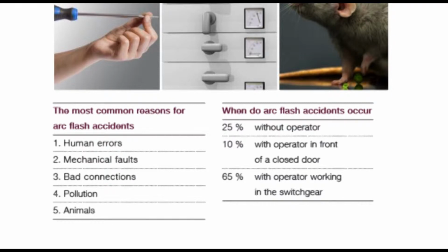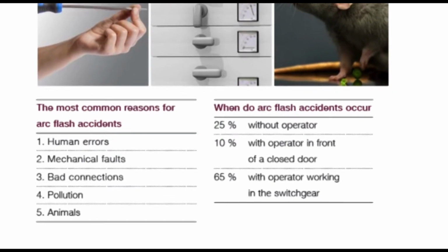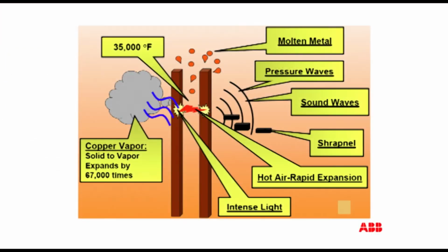But what's interesting to note is the percentage of arc faults and the reasons why. You'll find that approximately 25% happen without the operator being near the switchgear, about 10% with the operator in front of a closed switchgear, but 65% when the operator is actually working on the switchgear. So that statistic is very interesting to note.